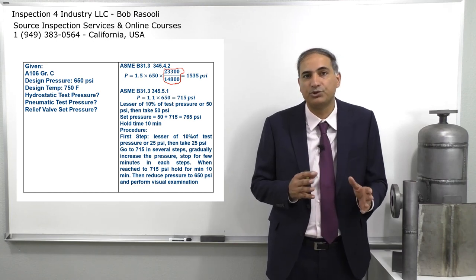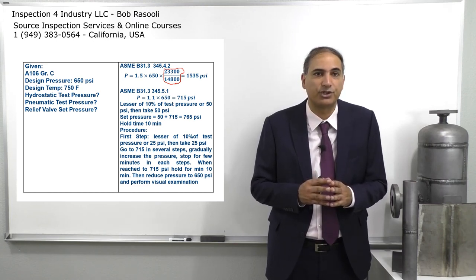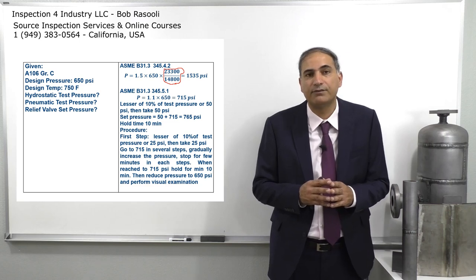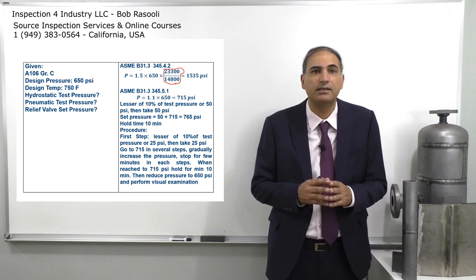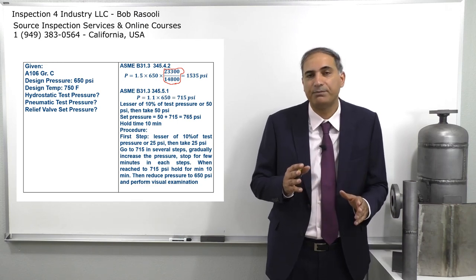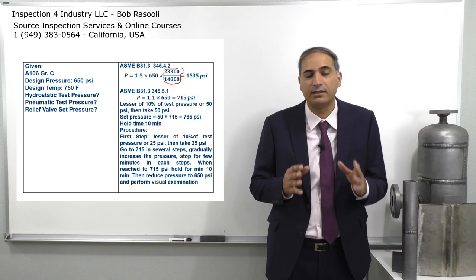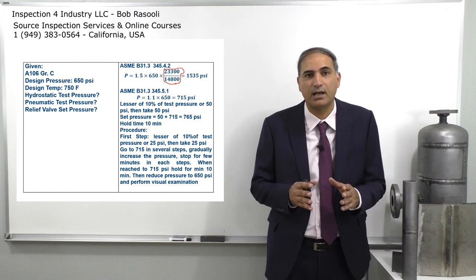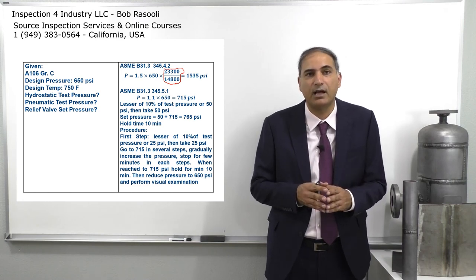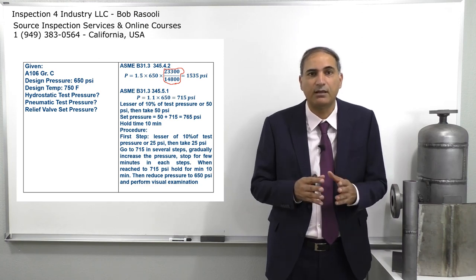Next, we check the relief valve set pressure. The code says take the lesser of 10% of the test pressure or 50 psi. Ten percent of 715 is 71.5 psi, and 50 psi is less than 65 psi, so we take 50 psi. Adding 50 psi to the test pressure of 715 gives us 765 psi as our relief valve set pressure.